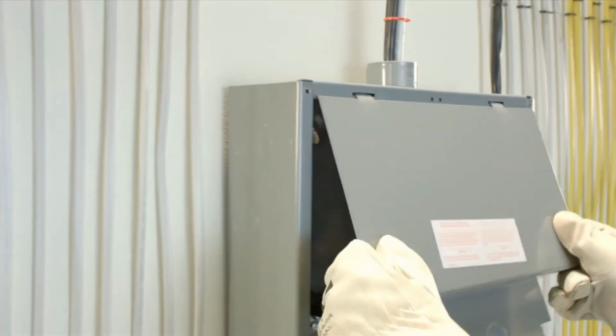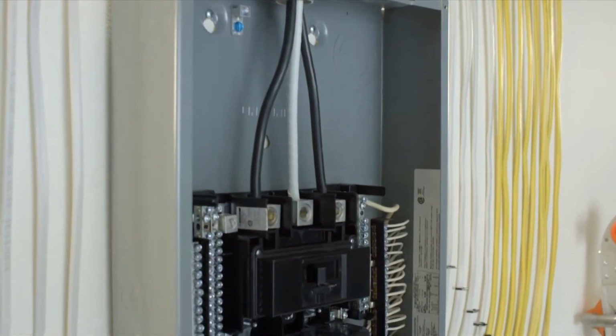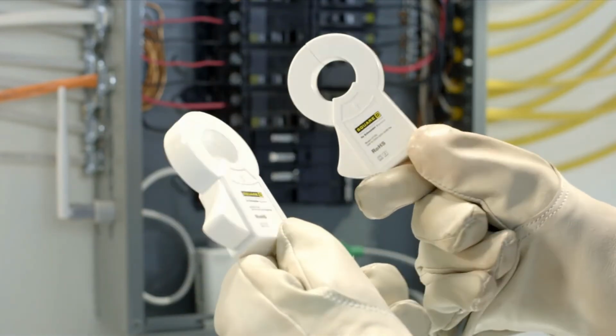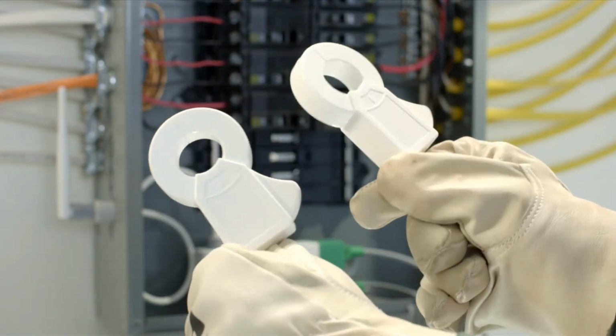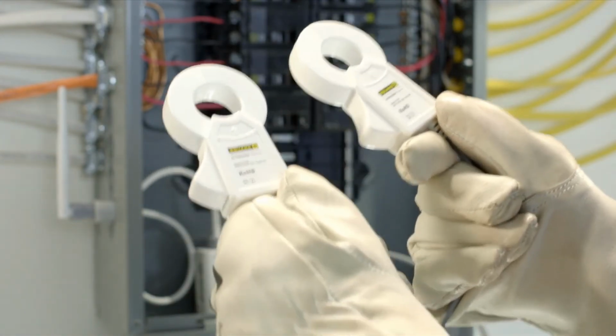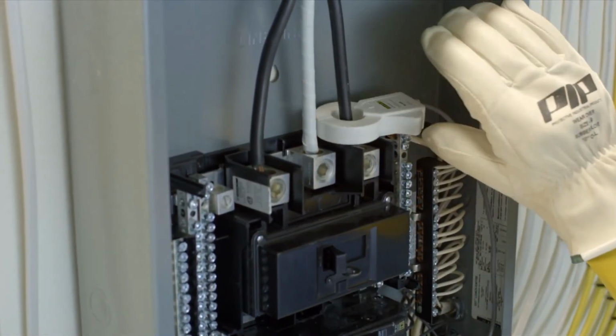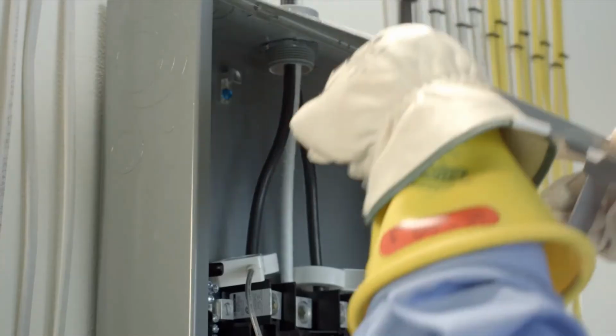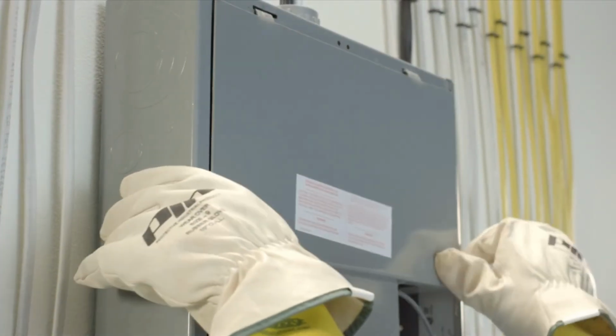monitor first. After removing the main breaker barrier, clamp the current sensors around the 2 main service cables, being sure the product labels on each sensor are both facing the same direction. They need to remain securely closed around the main service cables. Then, reattach the main breaker barrier.